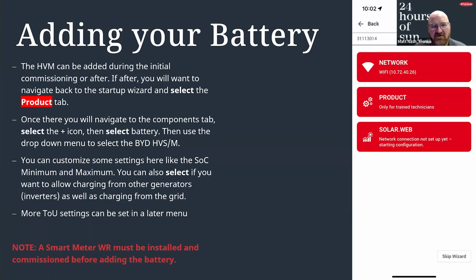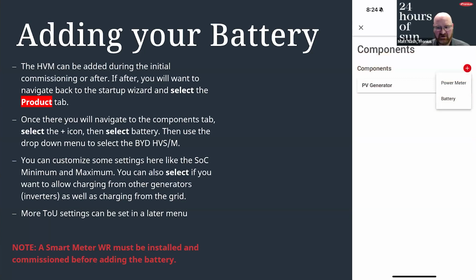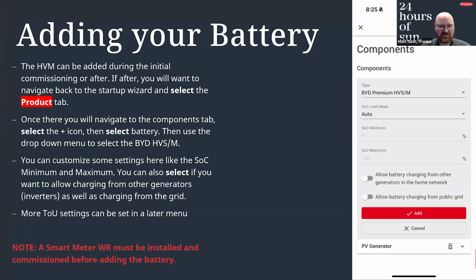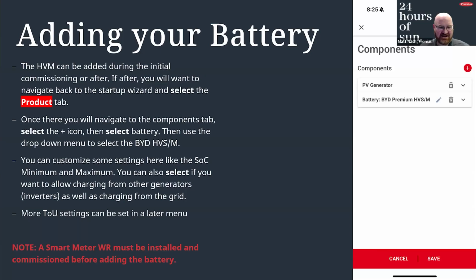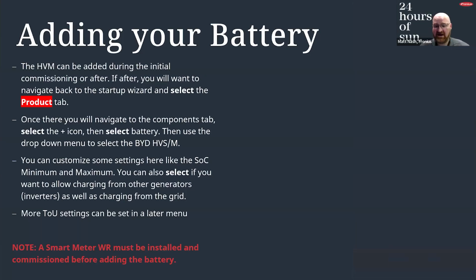So here's what you would do if you're going to add a battery. You can do it as you're commissioning the inverter, or you can also set it up if you're adding it after the fact. So you would go in, you would add the battery. So this is one of them. Now you can set it up for different state of charge settings. More often than not, you're going to leave that as auto and let the inverter tell the batteries what to do. You can set up more time of use things later. One thing to note, and I did say this earlier, I do believe, is you will need a smart meter in the system before you add the battery, because the inverter needs to know what's being consumed for the system.